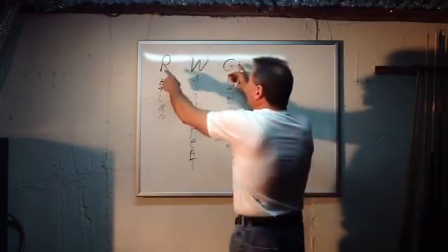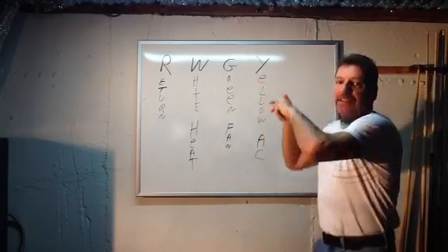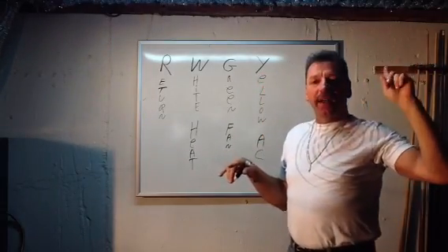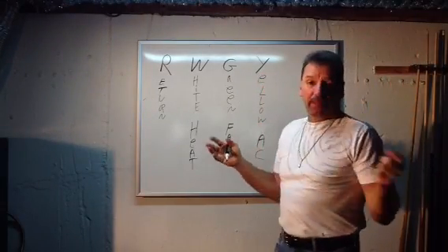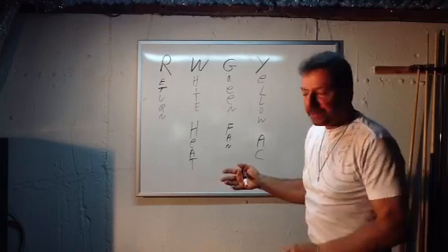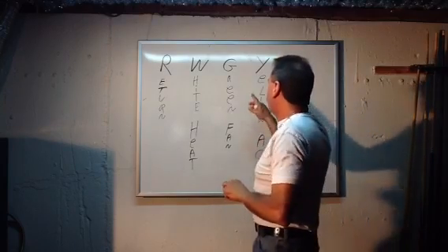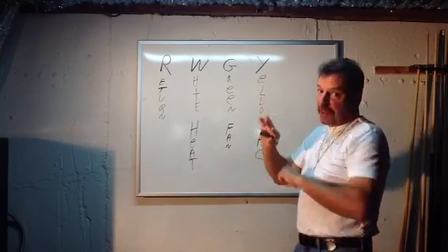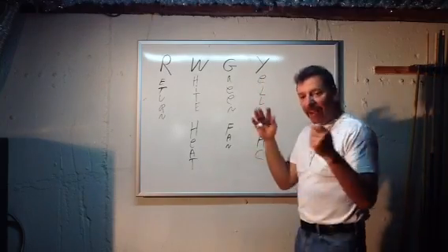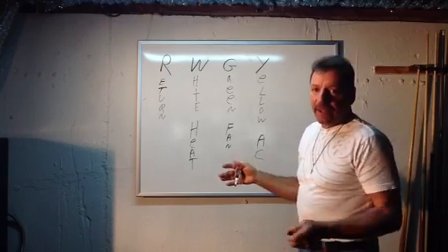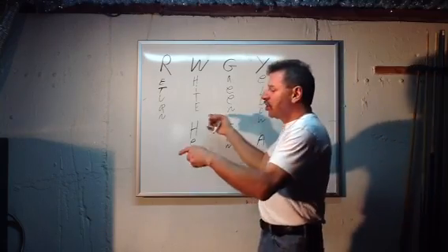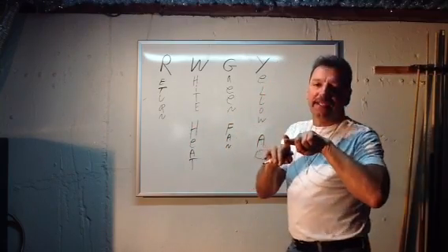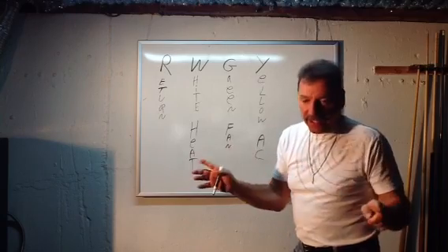If you twist the red and green together, the system fan would come on. You may want to do that during a party if everybody's smoking. If you twist the red, green, and yellow together—this is with the thermostat off the wall now—your air conditioning would come on. So the thermostat simply shorts the proper two wires together. That's all it does.